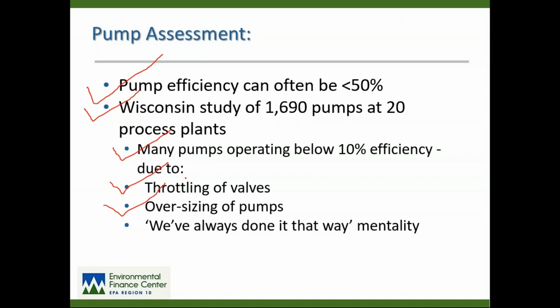Very often pumps were oversized because facilities are often designed for peak capacity rather than efficiency. So the engineers are making design decisions based on the life of a treatment plant or the life of a project, which might be 40 or 50 years, and designing it to operate at the population that you might have in 40 or 50 years. So we have often seen pumps and motors that are way oversized for the amount of work that they're doing. And they are basically just wasting a lot of money on energy. And also the good old "we've always done it that way" mentality. And we're not about to change because everything's working fine.